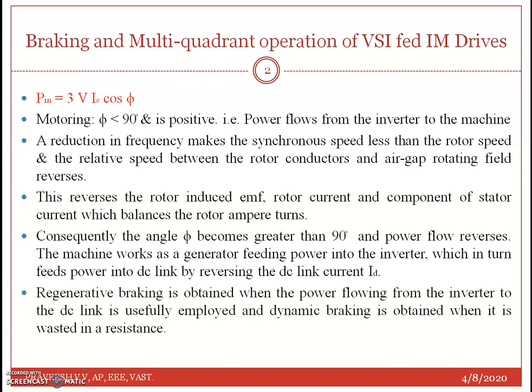Regenerative braking is obtained when this power is usefully fed back to the supply mains, and dynamic braking is obtained when it is wasted in resistance. So that is the basic working principle: power = 3·V·Is·cos(φ); φ less than 90 degrees is motoring operation with power flowing from inverter to machine, and φ greater than 90 degrees is braking operation.